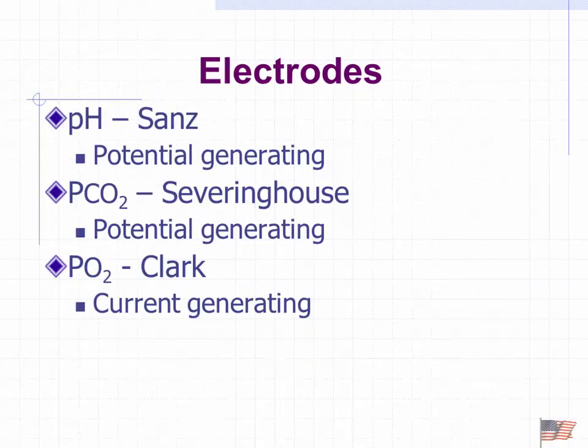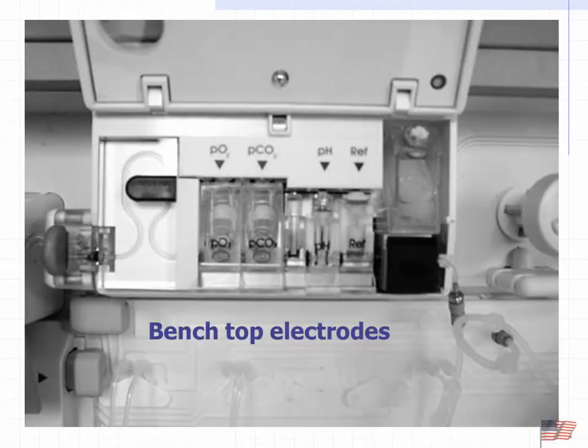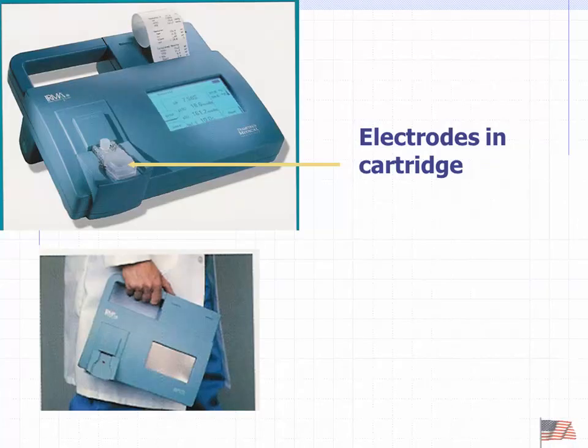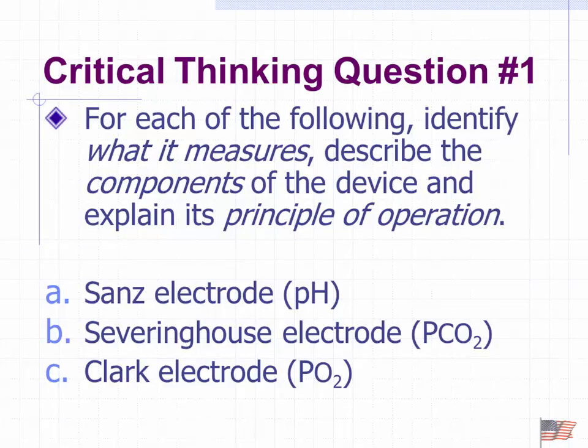So let's talk about those three electrodes again. This is the part that probably is the most confusing of all. The first two are potential generating electrodes, the pH and the PCO2, and how they work I'll explain in a second. The third one, the Clark electrode, is a little bit different. It generates a current. So here's what they look like inside the machine, and again they're inside that little plastic cartridge is where the electrodes are.